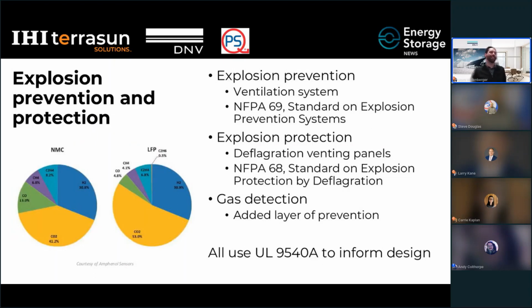When we look at gas composition data from cell-level tests in UL9540A, typically we see between about 30 and 50% hydrogen in these gas mixtures. Hydrogen is a very reactive gas, so it's important to have robust explosion prevention and protection systems within the container. Using this gas composition data, as well as gas volume data from module-level tests, we're able to put these into models for the battery container.